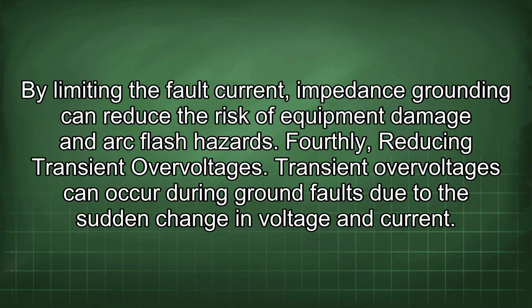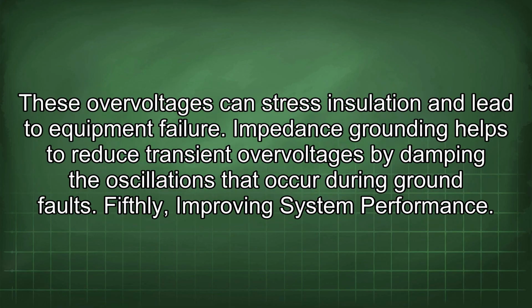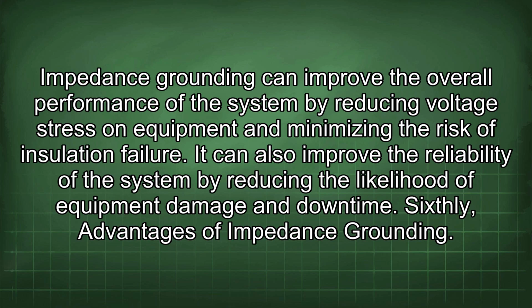Fourthly, reducing transient overvoltages. Transient overvoltages can occur during ground faults due to the sudden change in voltage and current. These overvoltages can stress insulation and lead to equipment failure. Impedance grounding helps to reduce transient overvoltages by damping the oscillations that occur during ground faults. Fifthly, improving system performance. Impedance grounding can improve the overall performance of the system by reducing voltage stress on equipment and minimizing the risk of insulation failure. It can also improve the reliability of the system by reducing the likelihood of equipment damage and downtime.